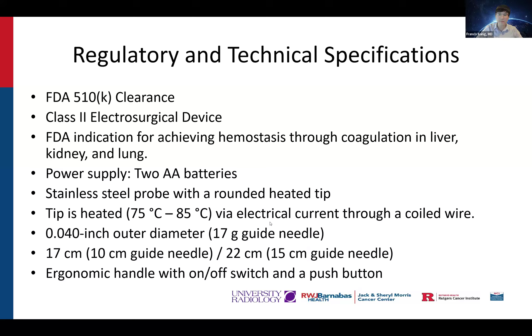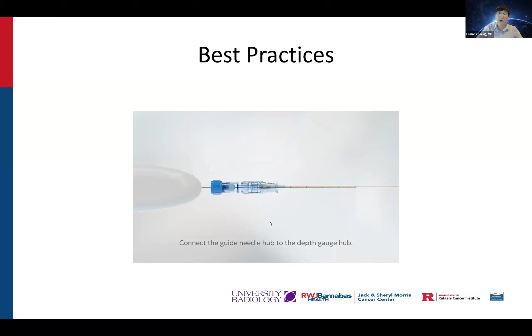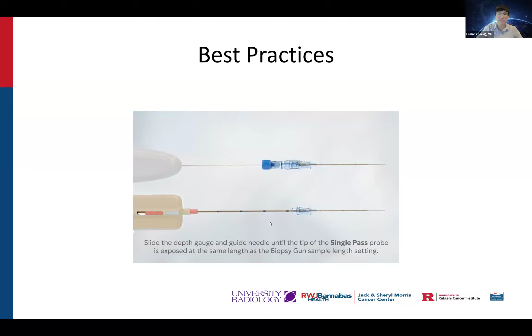Before single pass device is used, we need to prep the device prior to starting the biopsy. First, remove the sharp stylet from the guide needle. Place a single pass probe into the guide needle, then connect the guide needle hub to the depth gauge hub. Slide the depth gauge and guide needle until the tip of the single pass probe is exposed at the same length as the biopsy gun sample length setting. Twist the depth gauge to secure it in place at the adjusted position. Make sure it's very tight.